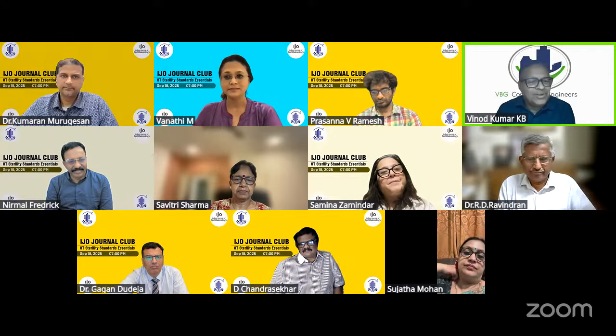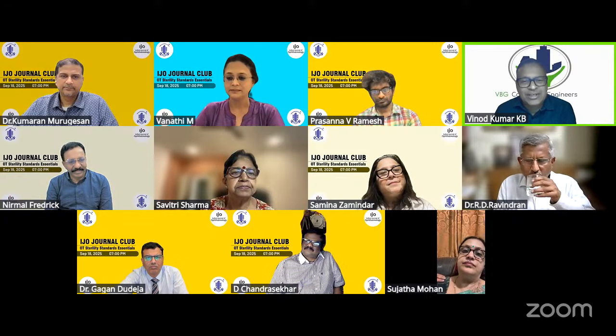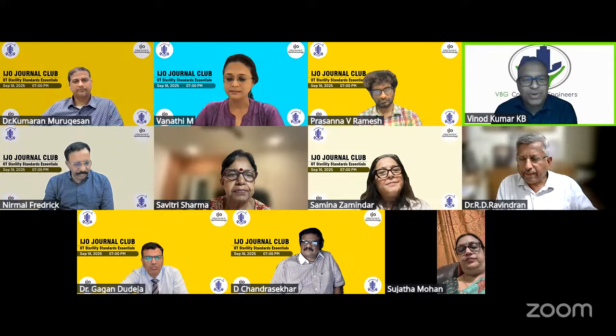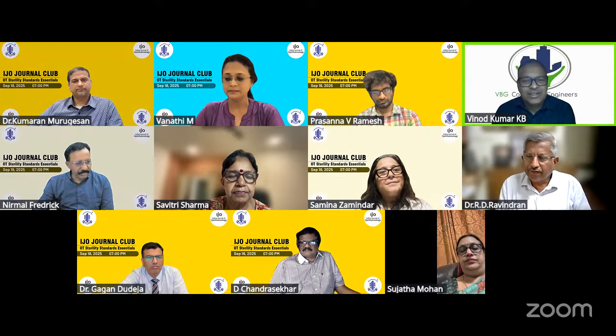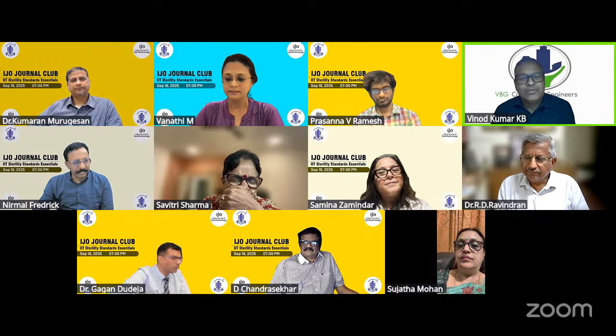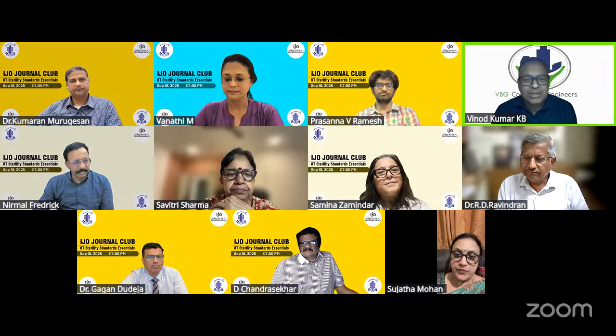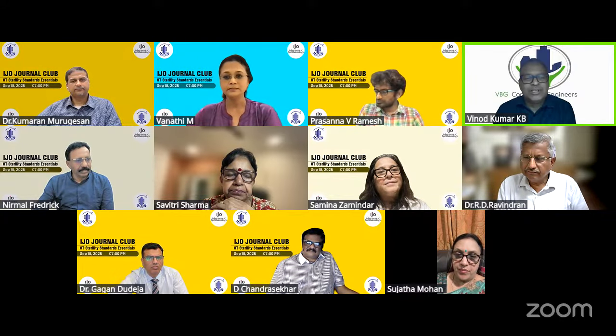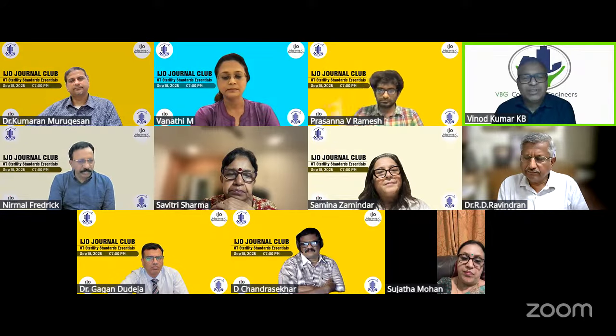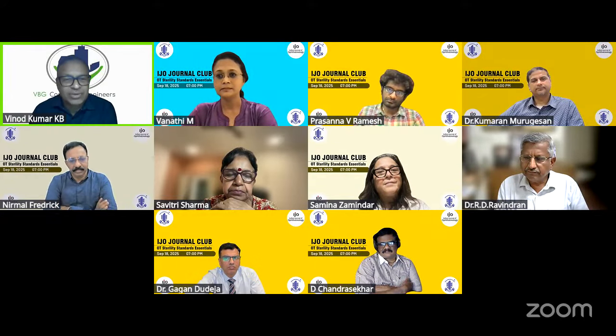Thank you, Dr. Samina. Yes, AHUs can fail, obviously. We need to make sure we buy the right product in the first instance. There are various kinds of air handling unit suppliers and various types of air handling units. There are air handling units generally used in commercial applications which sometimes get used in hospitals, which should be avoided, because healthcare systems, when it comes to ASHRAE or British standards, have specifications for the construction of an air handling unit.